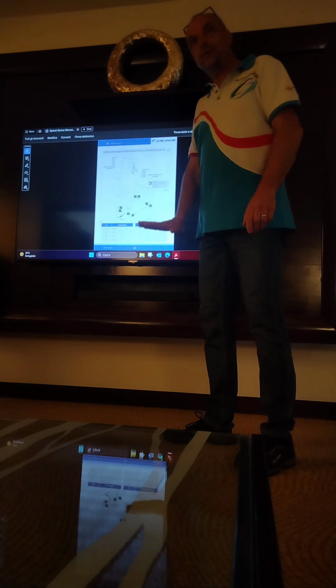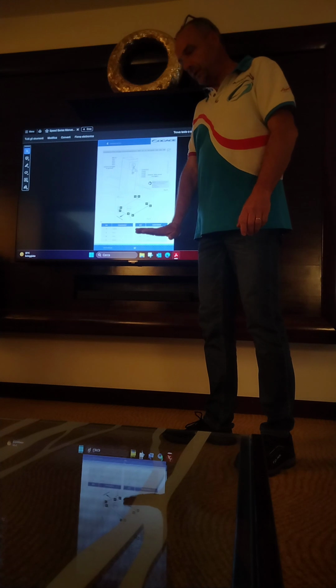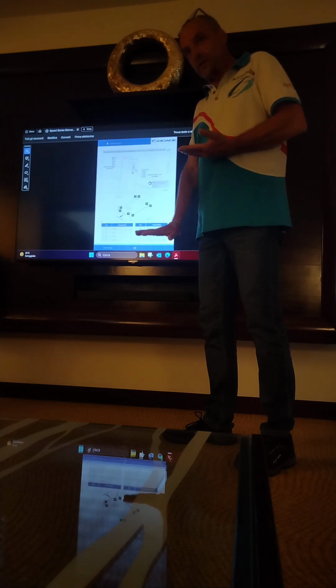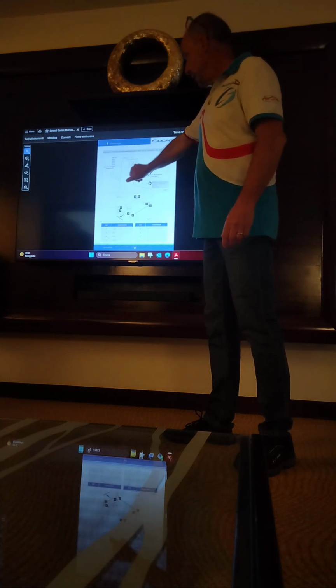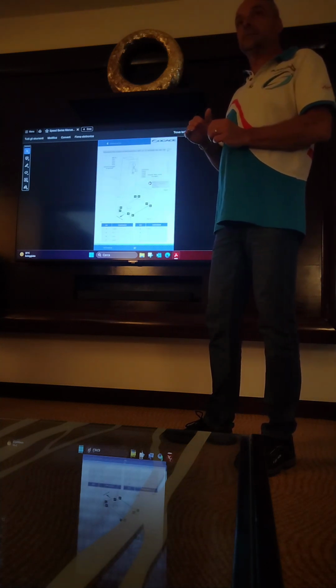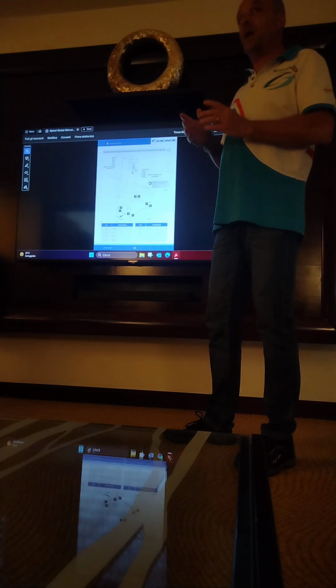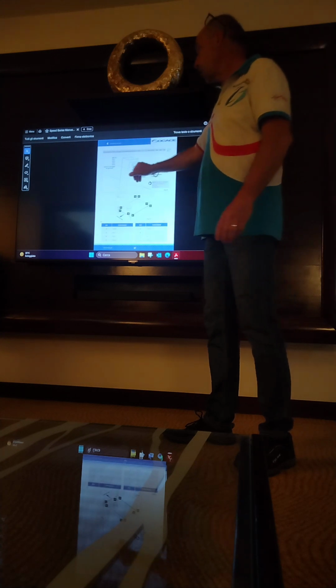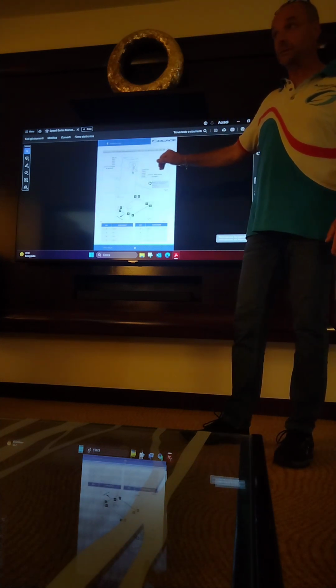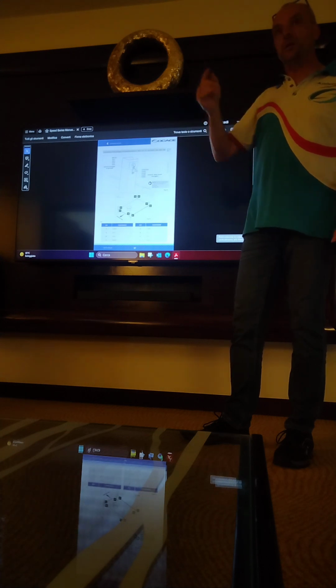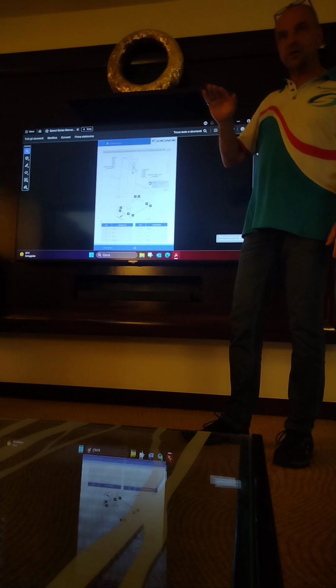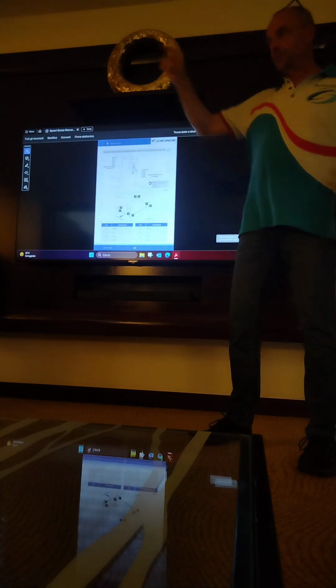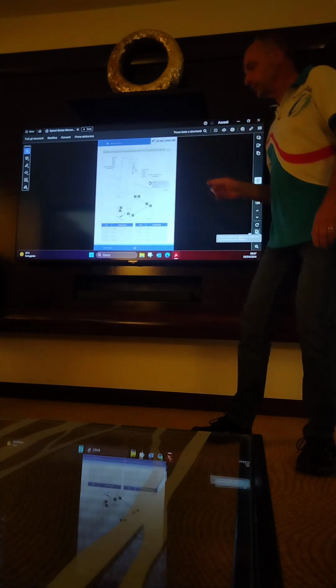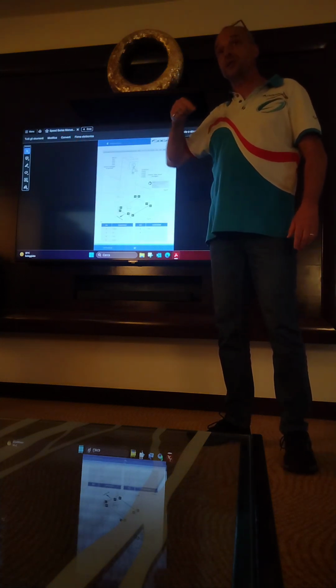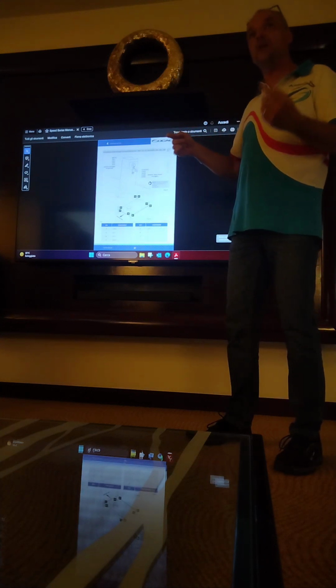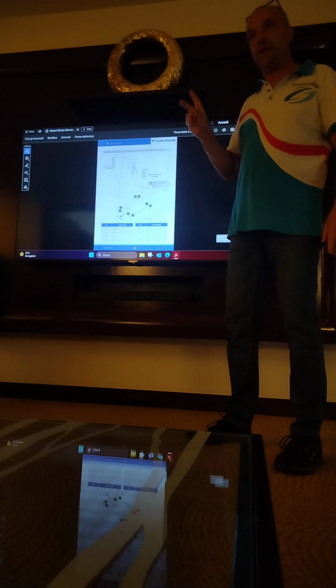Because this pin must move. When you push the outrigger on the ground, the pin moves up, and what happens is this switch becomes free. So we have, this is a normally closed contact. Why? Because the whole circuit, remember, even for the smaller machine, has 5 contacts, 1, 2, 3, 4, 5, forming a closed circuit. If one of them is open, you don't have the okay signal.